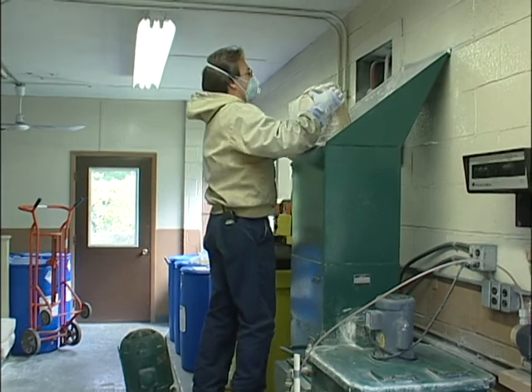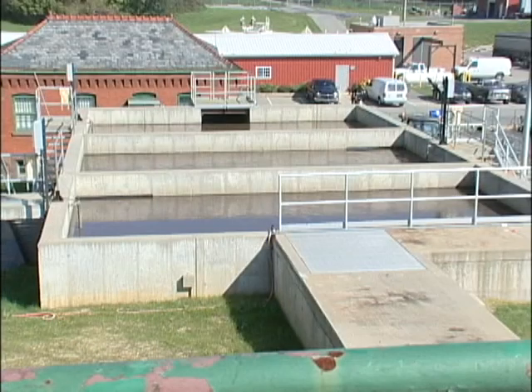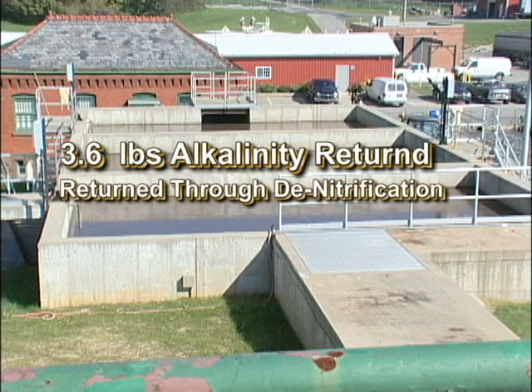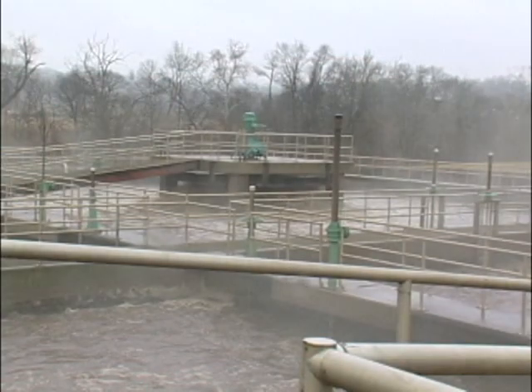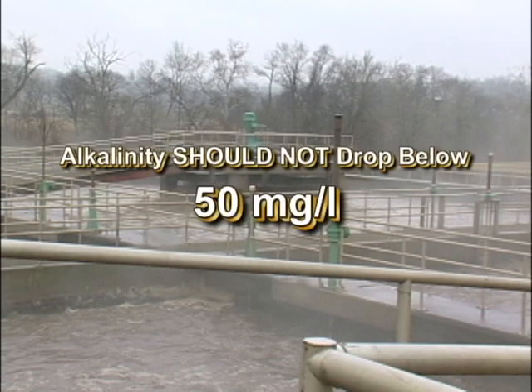It should be noted that for facilities that have an upfront anoxic zone for denitrification, approximately one half of the alkalinity that is consumed for nitrification is returned to the system through denitrification. As a rule of thumb, the alkalinity should not drop below 50 milligrams per liter at any point in the process.